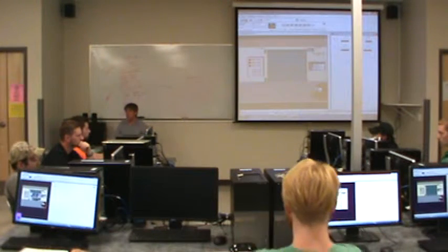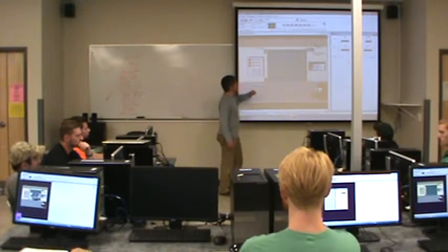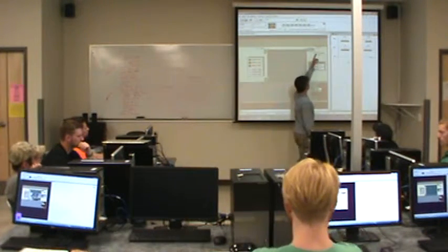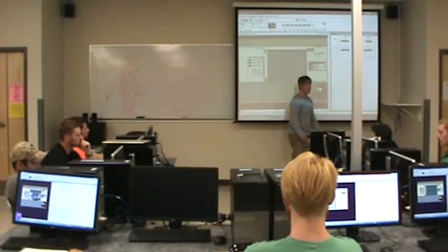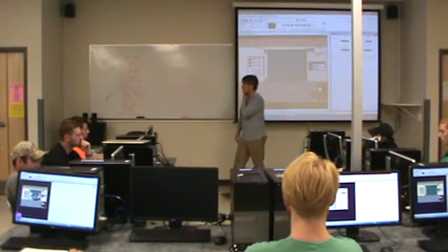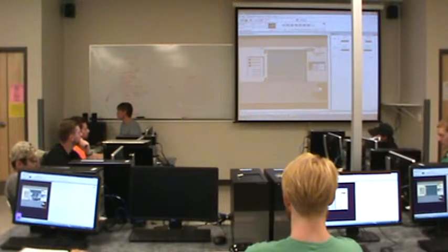All right. Now the addresses are I1/0 for open, I1/1 for close, O2/0 for the output up, and O2/1 for the output down. Okay? Now if I run this, it'll do exactly what you expect. Download, run. If I press the open button, the door starts moving up.